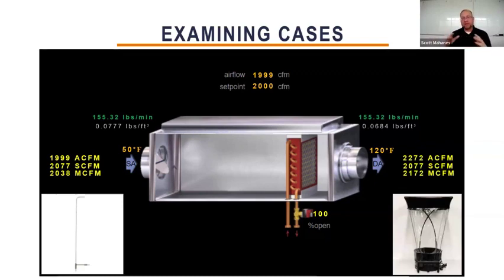And if you want to go do this test, you take a calibrated airflow sensor at 50 degrees and you're perfectly calibrated, increase the discharge air temp to 120 degrees, and you will see a distinct difference between what you measure and what the airflow sensor shows. Not because the calibration gets wonky, it's because the volume has to go up because the density's gone down. And if I were to calibrate this sensor based on what I measured on the discharge side of this box at this condition, I would be miscalibrating this VAV flow sensor by, I think it's 13 or 14%. So it would be a big error to have.